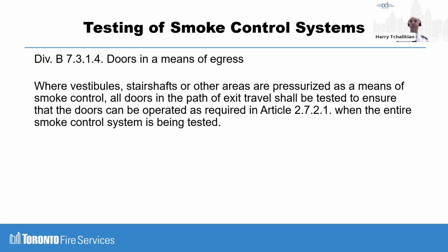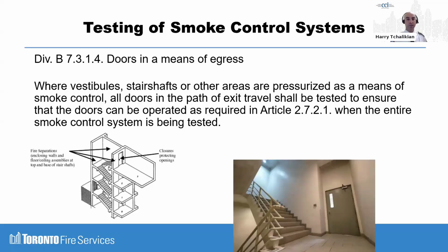Next, doors in a means of egress under Part 7. Where vestibules, stair shafts, or other areas are pressurized as a means of smoke control, all doors in the path of exit travel shall be tested to ensure that the doors can be operated as required in Article 2.7.2.1 when the entire smoke control system is being tested. So finally, they put this in here.